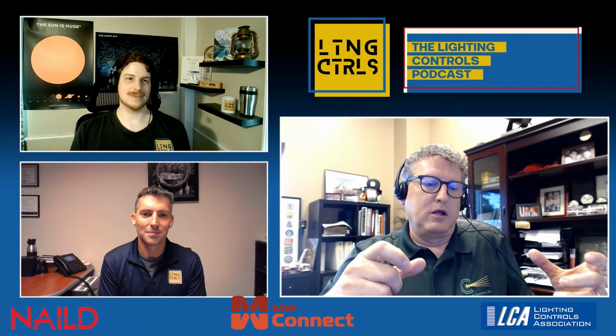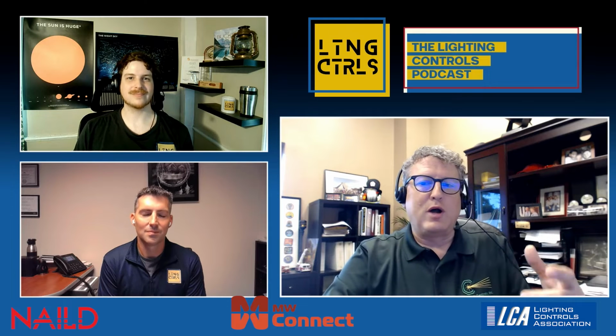But you've got to get this all tied together. You've got these controls that you want to work, and that lighting needs to come on to get the CO. Sure, you could cheat and disconnect it from the controls at the panel so it's all on at full, but now it's on 24/7, and no owner wants that.